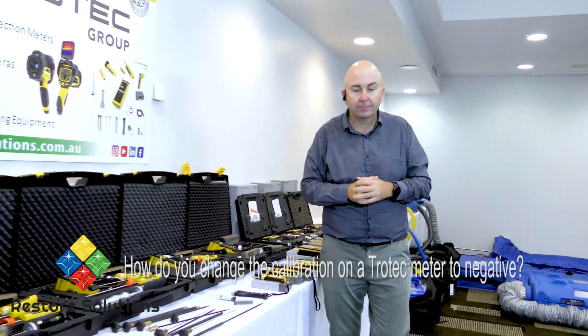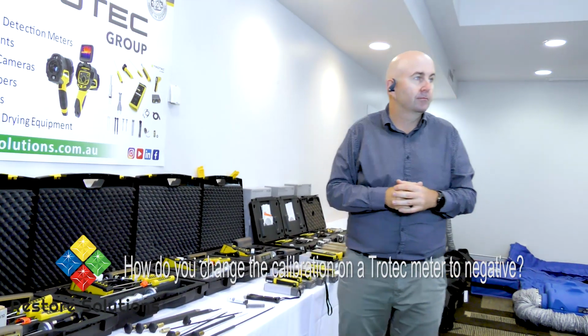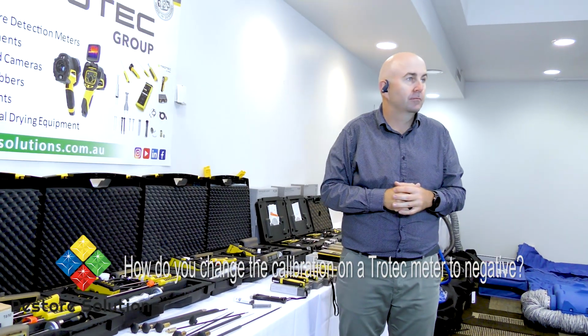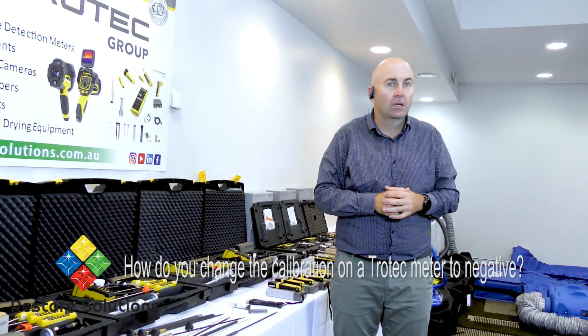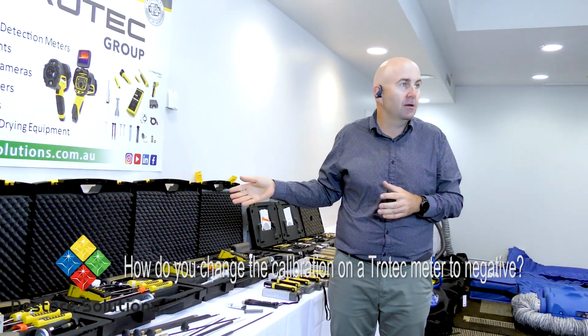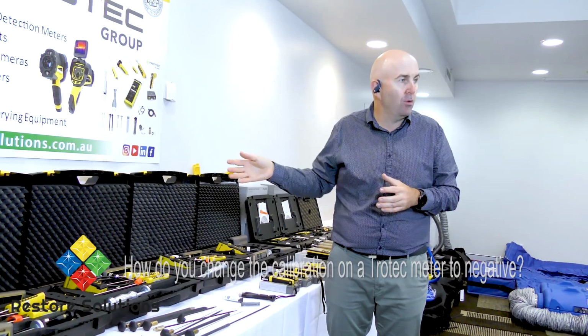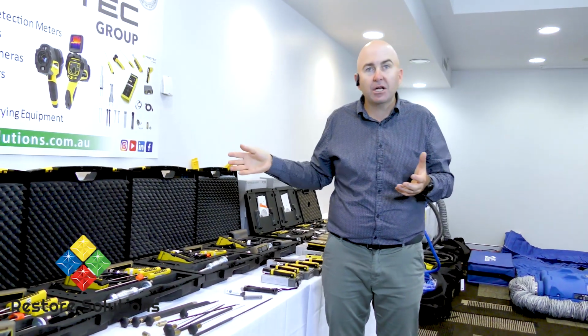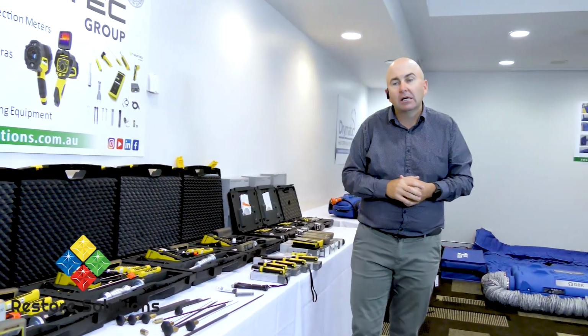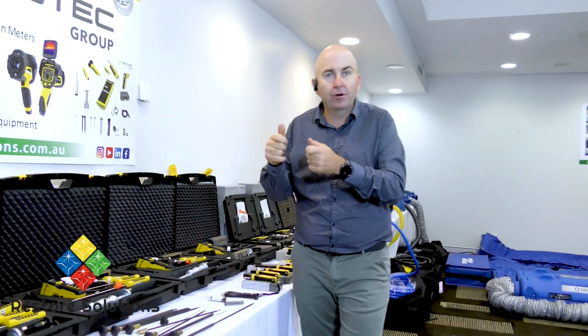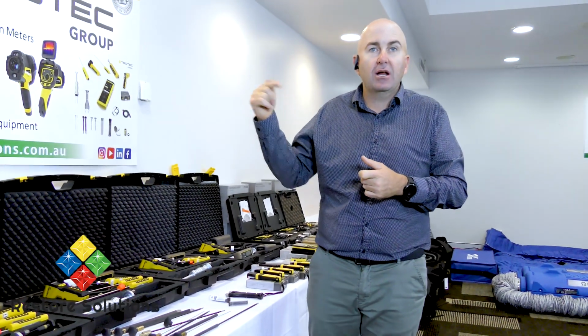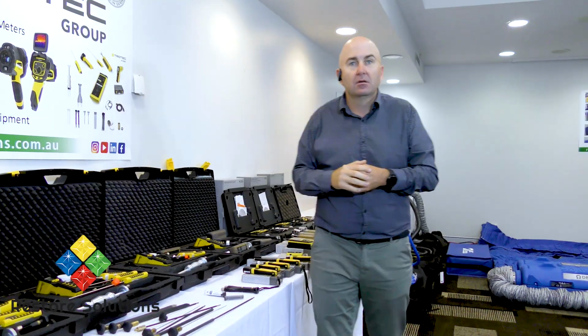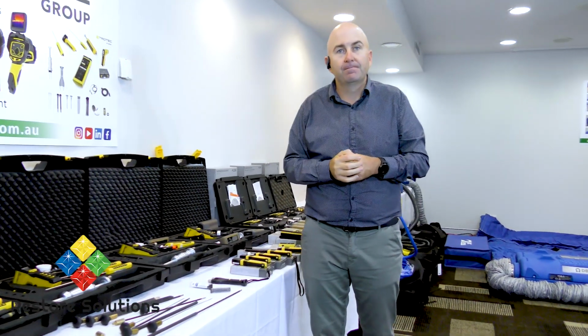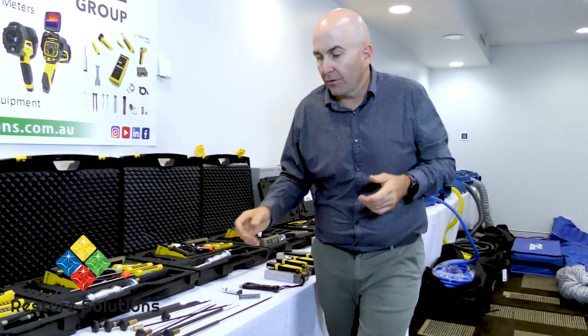I've got a question here, I'm not sure. How do you change the calibration on a Trotec meter to negative? Does that make sense to you? Well, you've got a plus and minus you can add. If it's out of calibration, you've got a plus and minus you can add. So you've got to go through in the calibration section and either add or minus to get it back to 0, or back to whatever reading it's supposed to be.